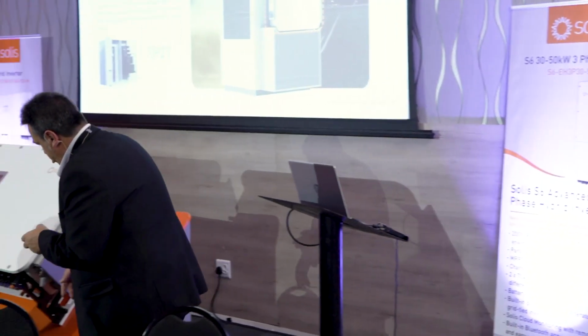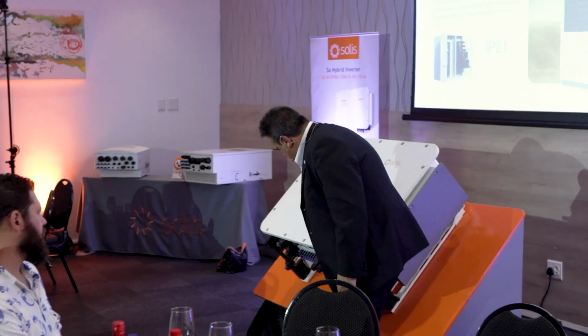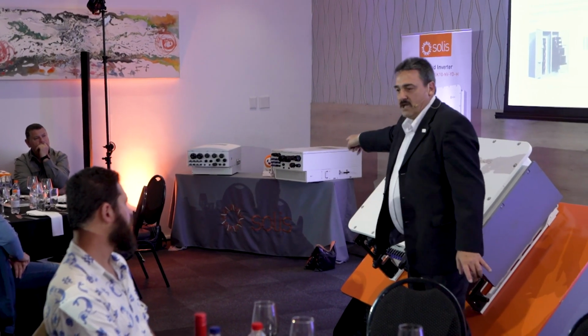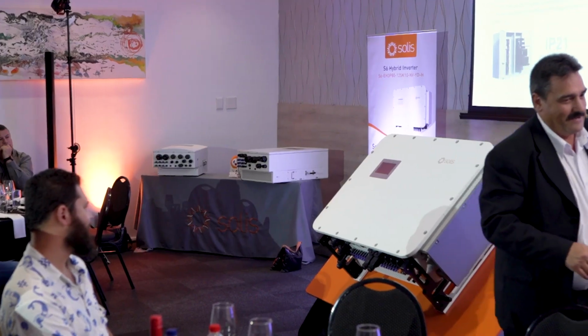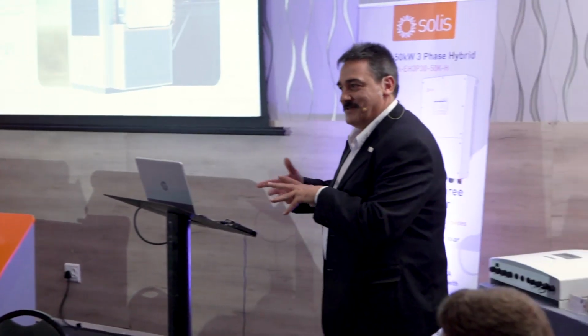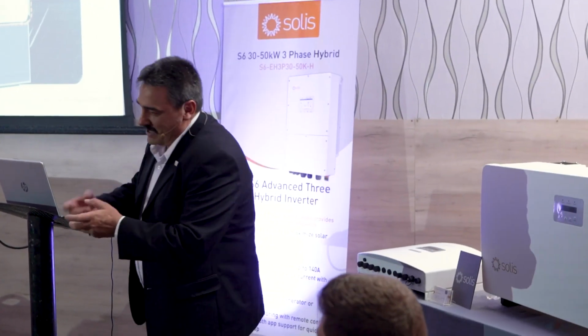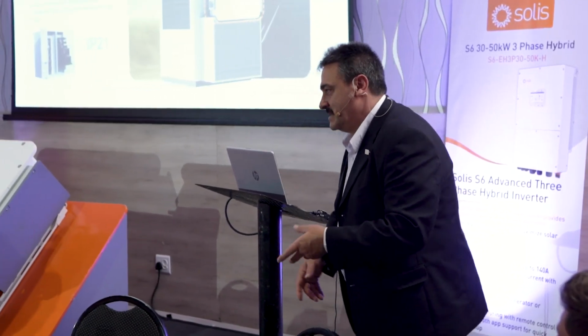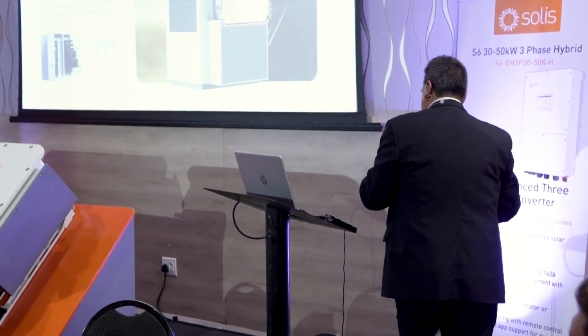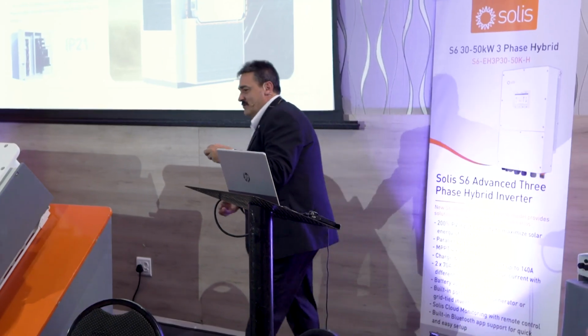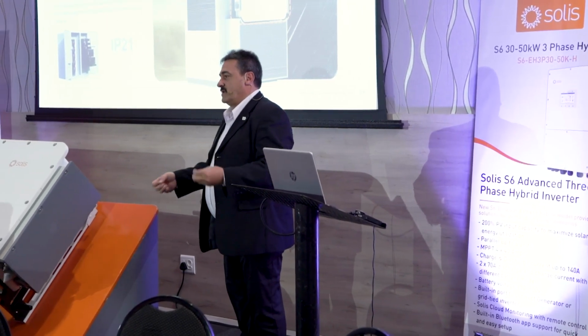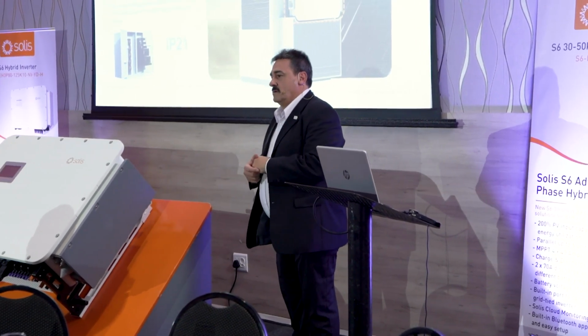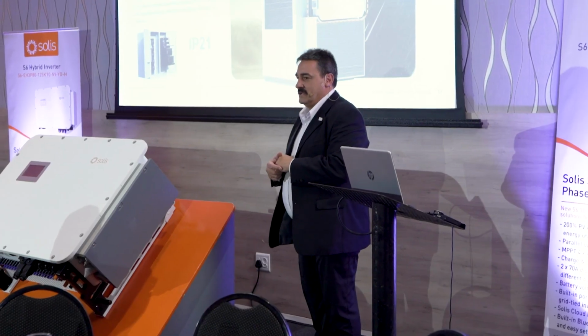This has also been a little bit redone apart from here. A lot of this, we've taken a lot of the small glands out, because what we've seen in the residential area, all the guys take all the glands out and bring all these little widespread tubing pipes in. And immediately when you take the gland out, what do you do? You ruin the IP rating of the product. It's gone, as simple as that.